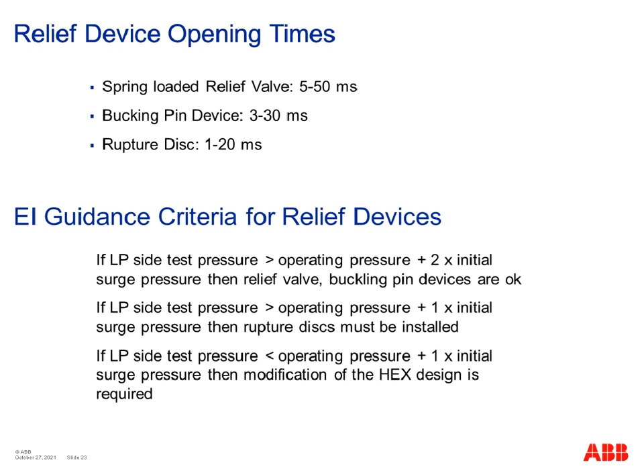If the LP side test pressure is actually less than the operating pressure plus 1 times the initial surge pressure, then modification of the heat exchanger design is required. So what that's saying is you're in a bad place at this point and you might need to go back to the drawing board, or you might need a whole new heat exchanger if this is an equipment item that's already installed on the plant. So that wouldn't be a good outcome.